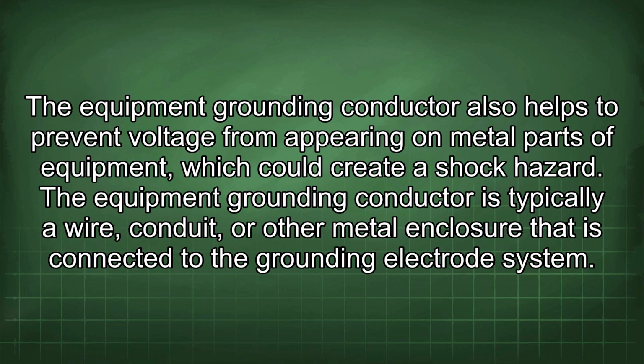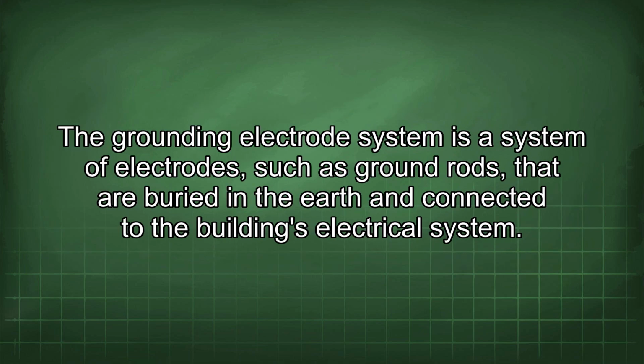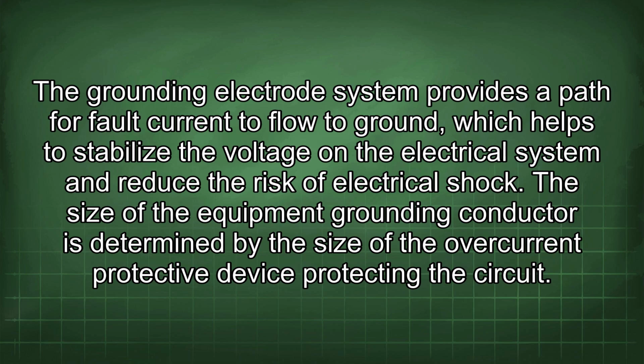The equipment grounding conductor is typically a wire, conduit, or other metal enclosure that is connected to the grounding electrode system. The grounding electrode system is a system of electrodes, such as ground rods, that are buried in the earth and connected to the building's electrical system. The grounding electrode system provides a path for fault current to flow to ground, which helps to stabilize the voltage in the electrical system and reduce the risk of electrical shock.